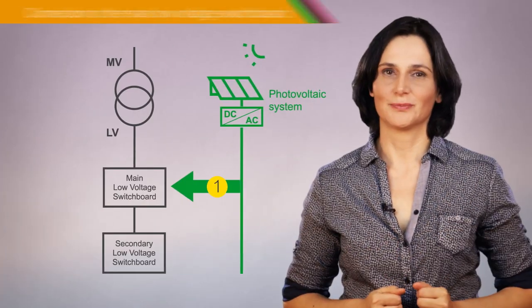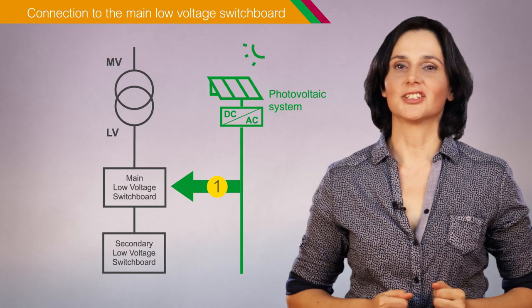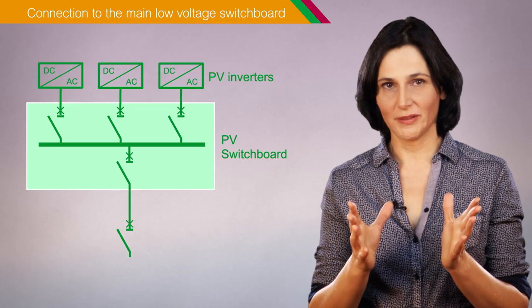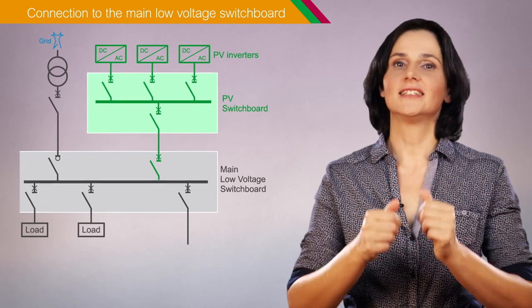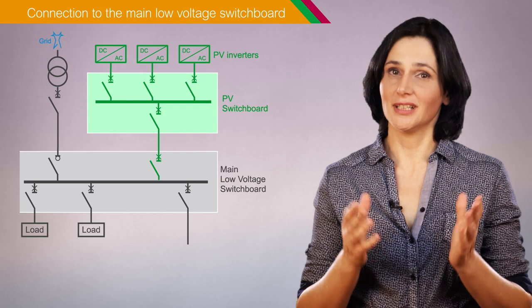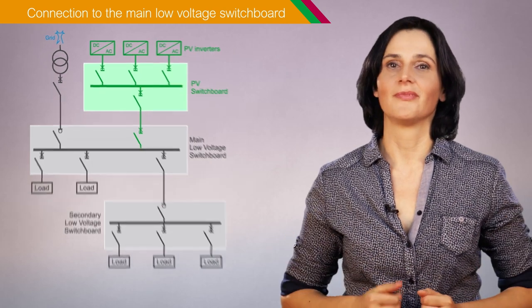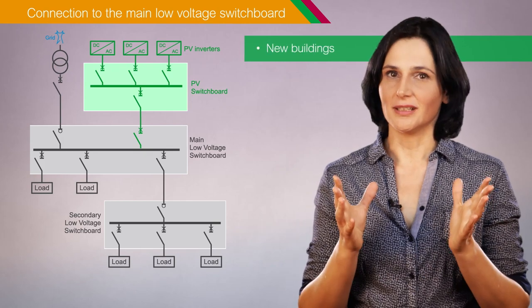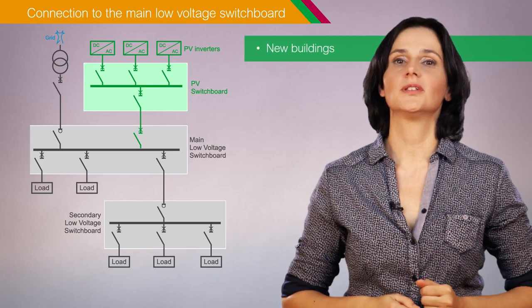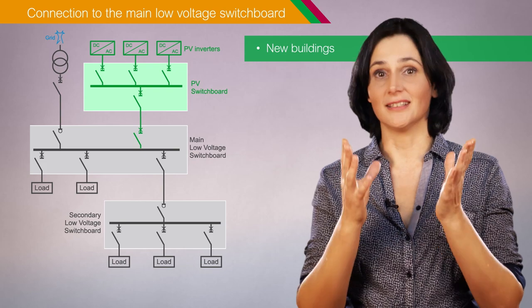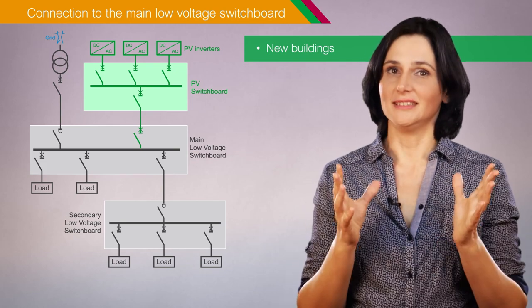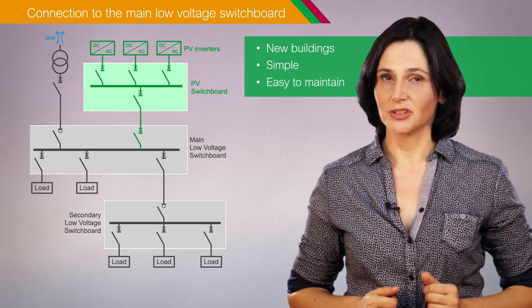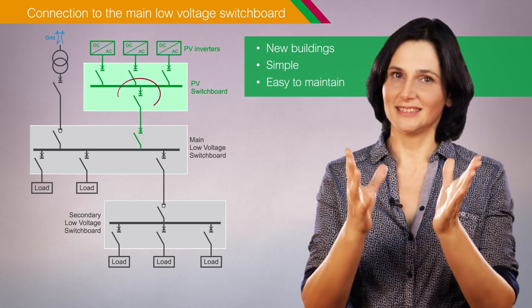First architecture. In the first architecture, the photovoltaic production, shown here with a group of three photovoltaic inverters, is connected to the main low voltage switchboard of the electrical installation. This architecture is suitable for new buildings where the installation is designed to take photovoltaic production into account at an early stage. It's simple and easy to maintain because the photovoltaic production can be disconnected at a single point.